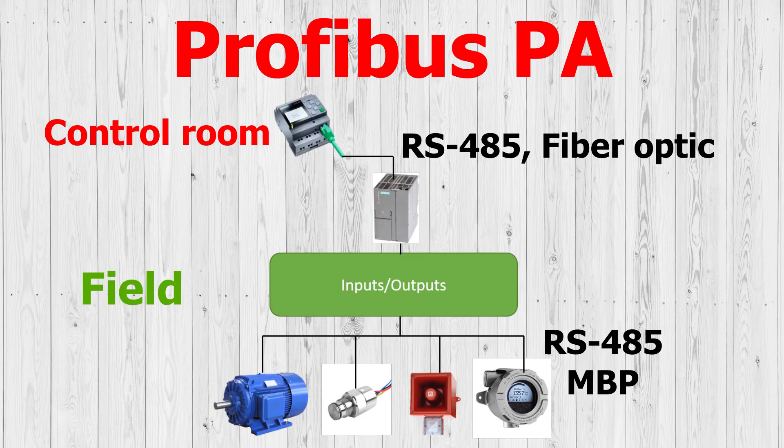However, Profibus PA still relies on Profibus DP to communicate with the control room, as many devices do not have special inputs for Profibus PA, so a coupler must be used to convert the Profibus PA signal to a Profibus DP signal. That's because the DP signal is faster.